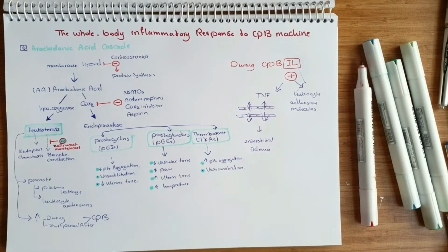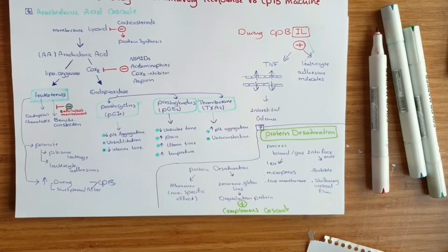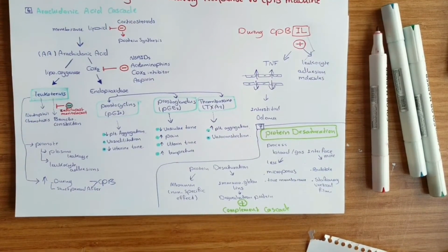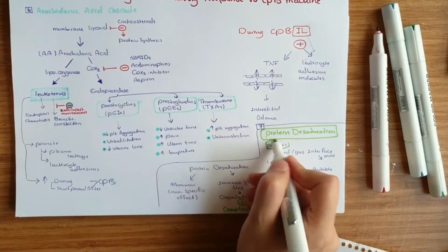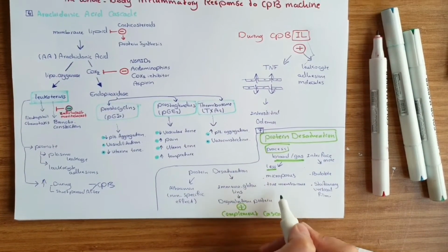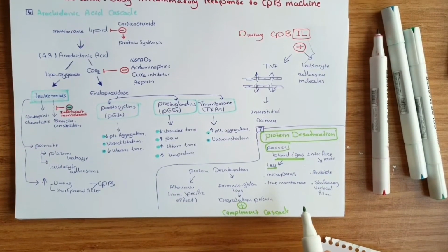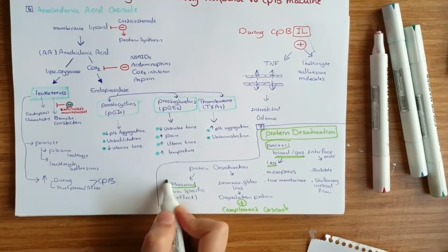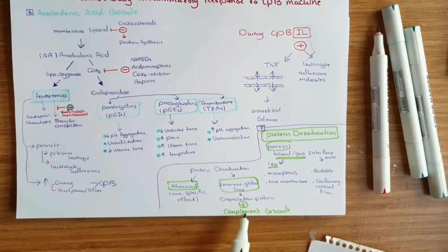Protein denaturation happens because of the blood-gas interface. The blood-gas interface is more with bubble oxygenators, and it is less with true membrane oxygenators. Protein denaturation occurs on albumin, which gives a non-specific effect, while for the immunoglobulin, when it is denatured, it stimulates the complement cascade.